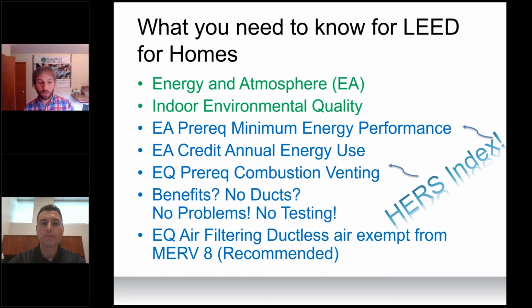However, and especially with the pandemic, we highly recommend higher levels, especially ones around 13 or so that can catch viral transmission issues. So you're better off to do it. Even though you're allowed to get away with it, we don't recommend going lower than that. So those are some of the quick ways this fits in with the LEED program.